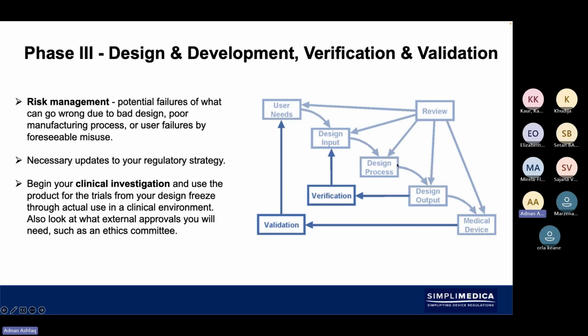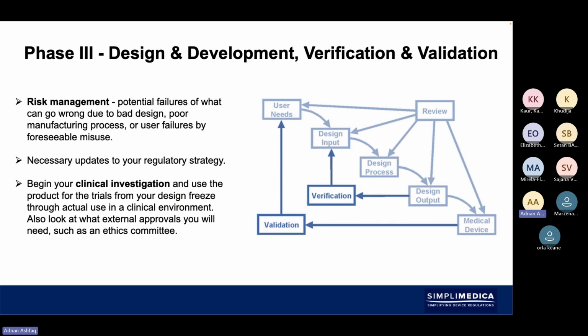This diagram that we've got here is a typical waterfall diagram, which looks at your user needs, design inputs, outputs, then verification and validation. And at each of these stages, we should have a design review meeting. And we need to make sure that we've also achieved design freeze so that we're not changing the design after a certain point. Once the design is frozen, we then look at clinical use, and also look at usability studies as well. You might need to have ethical approval from an ethics committee, and you might also need to run specific clinical trials. Again, that's if your evaluation doesn't allow you to have equivalence.